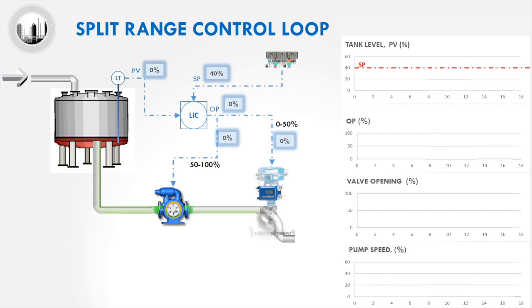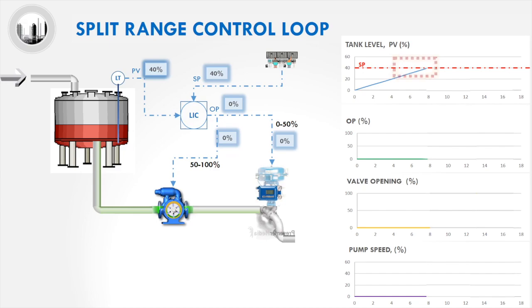We will now evaluate the actual behavior of the split range control when the tank level increases. When the level in the tank increases, the level transmitter's reading will increase. Since the tank level has yet to exceed the controller's set point, the controller's output will remain at 0%, and the valve opening and pump speed are also at 0%. When the tank level increases above the controller's set point, the controller's output will increase, and the valve opening will slowly increase to 100%. However, since the controller's output has yet to exceed 50%, the pump speed will stay at 0%. As the pump has yet to start, the tank level will not reduce back to the controller's set point, causing the controller's output to further increase. Once the controller's output value is above 50%, the pump speed will increase.